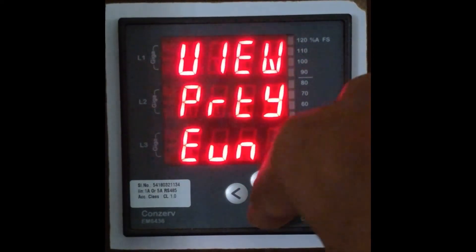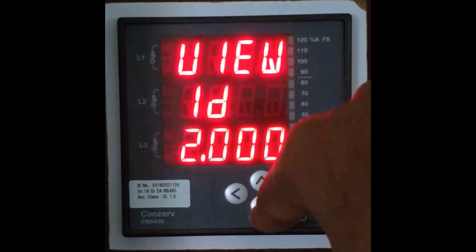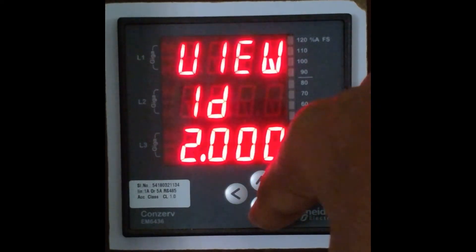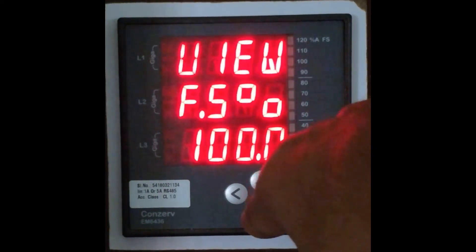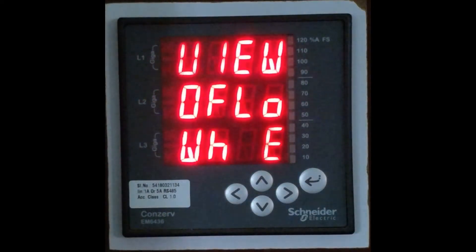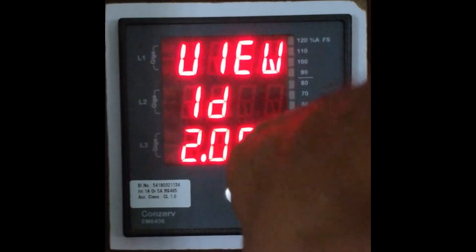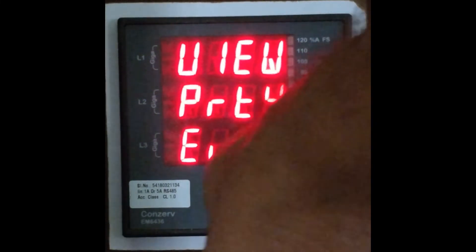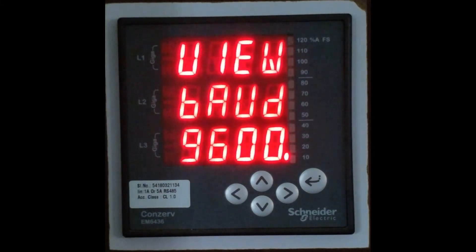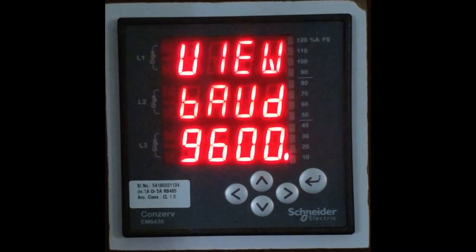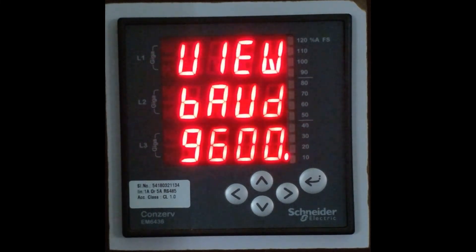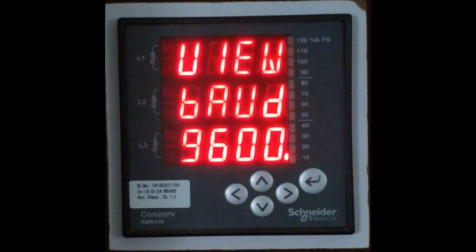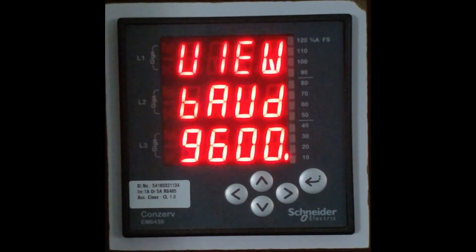Parity is the even. ID basically, the slave ID for the ModBus is 2. These are the other things - basically the important thing that we want is these parameters: the baud rate, the ID, and the parity. The meter in the picture is with an ID 2, but for the experiment or for the demonstration I will be reading with a meter that has an ID 1.